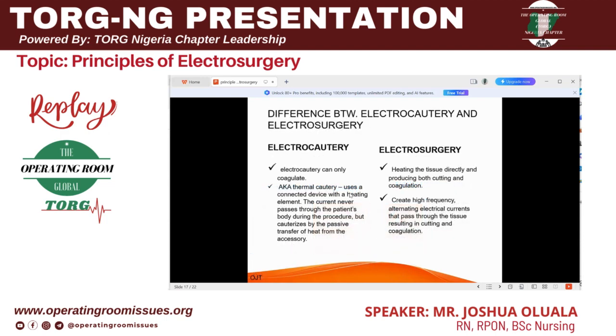Also, we need to know the difference between electrocautery and electrosurgery. Literally, these words are used interchangeably. Somebody talking about electrosurgery is talking about electrocautery. People assume that they are all the same. But in the real sense of it, no, they are different. Electrocautery is actually different from electrosurgery. Take, for example, electrocautery can only coagulate, while in electrosurgery, of course, we have both cutting and coagulation.